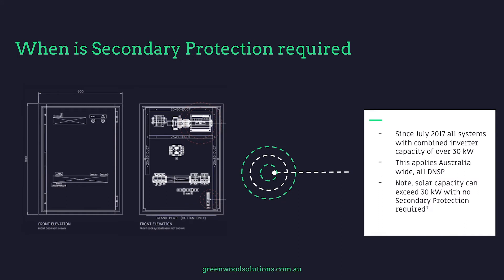Since July 2017, all systems with combined inverter capacity of over 30 kilowatts require secondary protection, and this is Australia wide — so all DNSPs. Note that solar capacity can exceed 30 kilowatts with no secondary protection required, as long as the AC is below that point. Remember, grid protection is secondary protection. The primary protection is effectively one of the functionalities of the inverters that you've installed. The secondary protection is there because the distributors have decided that their infrastructure needs further protection.